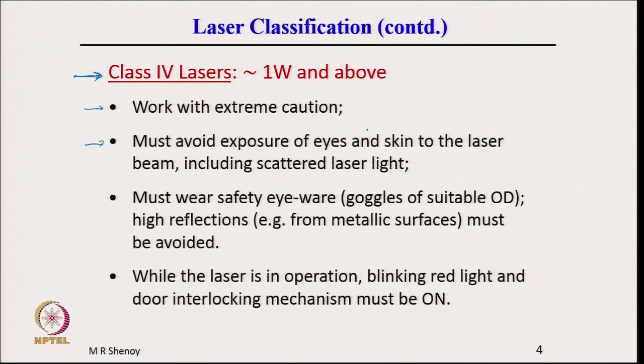for the class 3B, must avoid exposure of eyes and skin to the laser beam, including scattered laser light, must wear eyewear, goggles of suitable OD, optical density. I will discuss about this in the next slide. What is this OD? Suitable OD, and high reflections must be avoided.